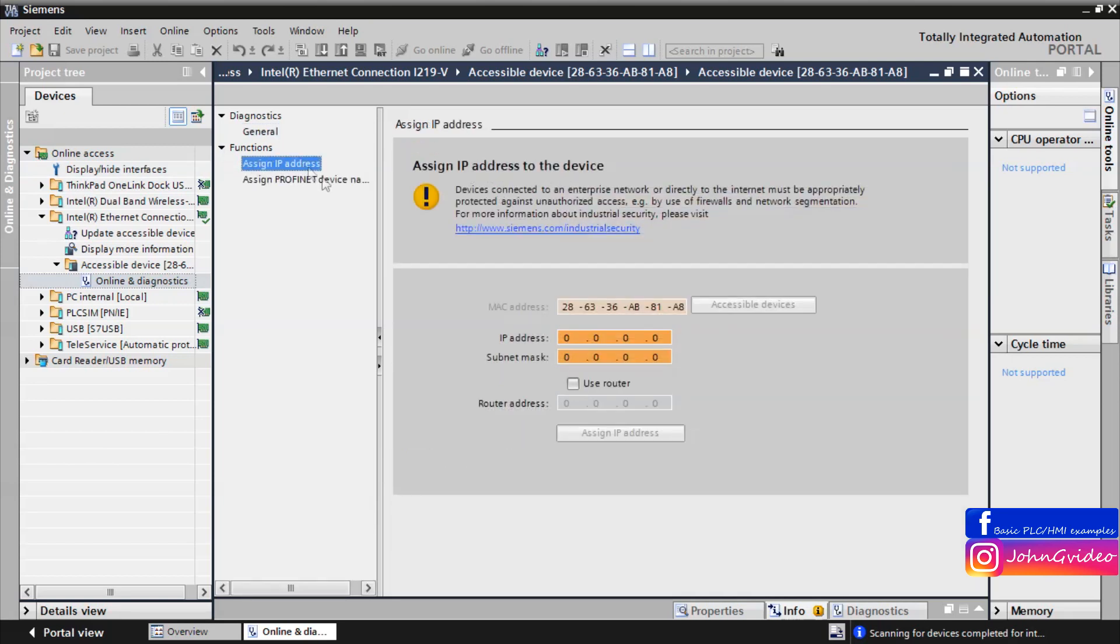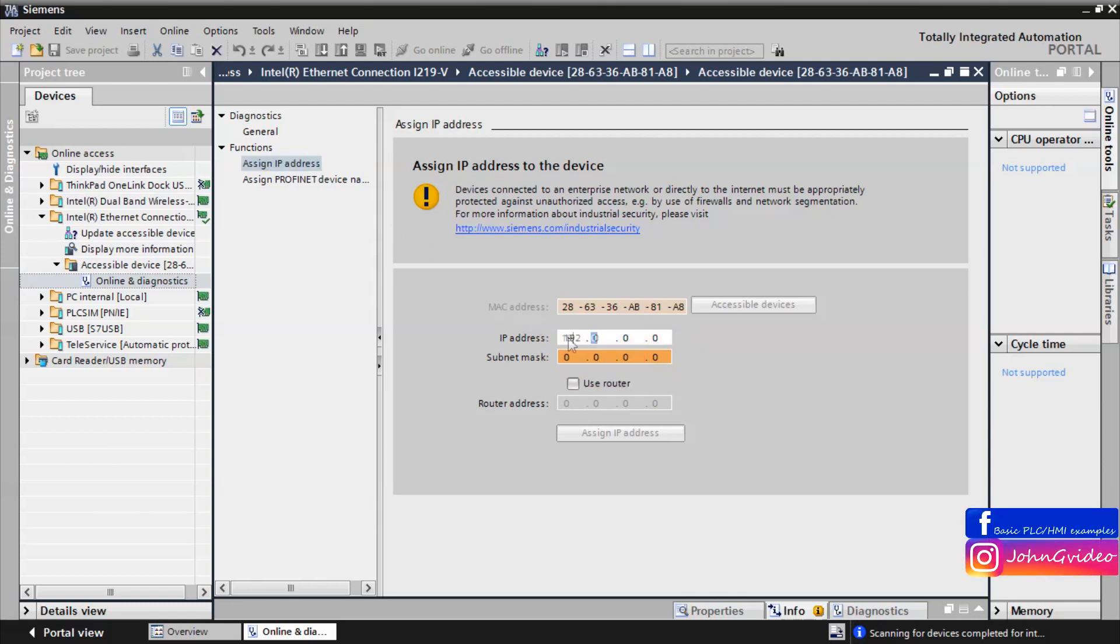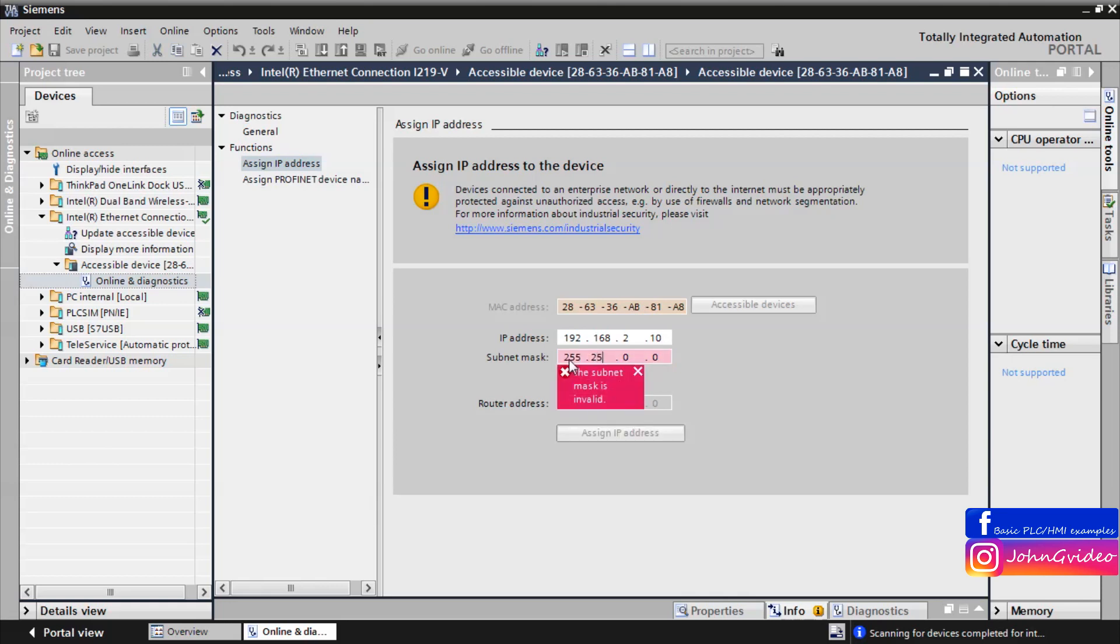In the IP address window, click on it and insert the IP address which you want to have in your PLC and also the subnet mask. After this, click on the assign IP address button.